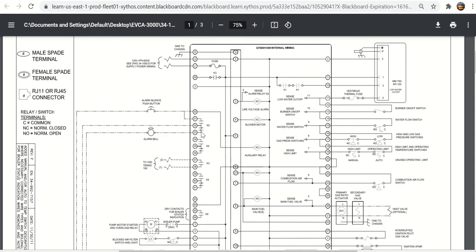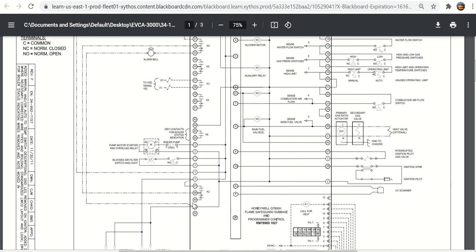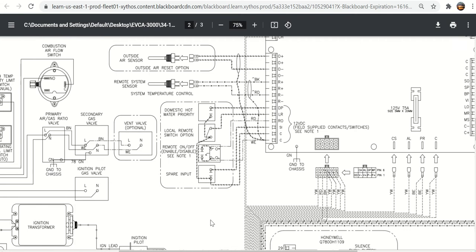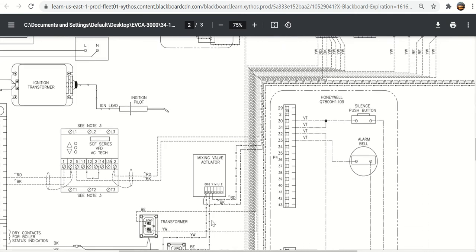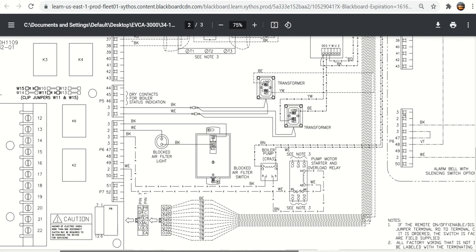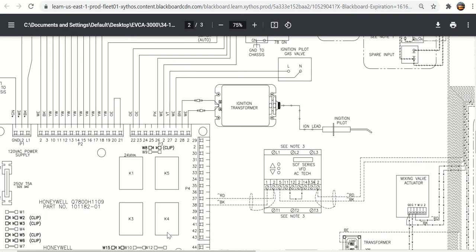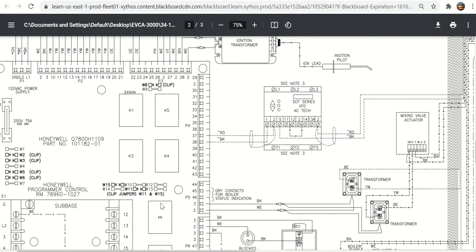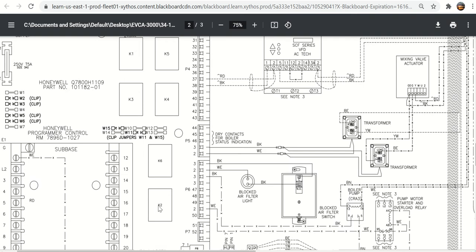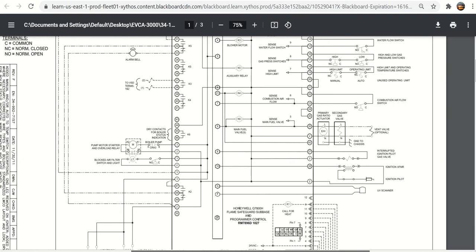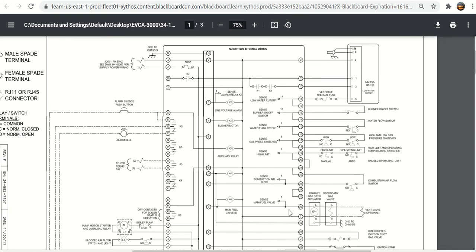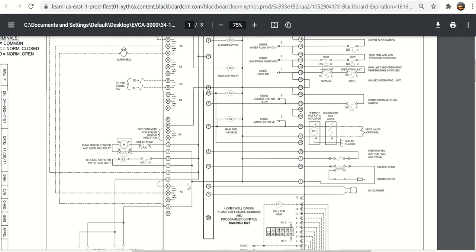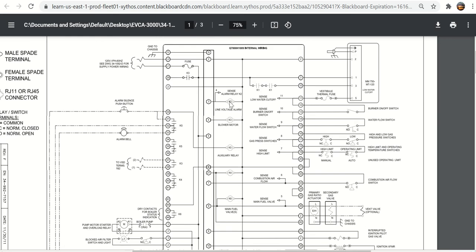I want to go over this alarm silence, alarm bell circuitry here. When you looked at this drawing down here on the circuit board where the 7800 subbase is, you see all of these K1. These are all relays. You saw K2 was the alarm relay, K5 was the blower relay. Here you have K2, which is the alarm relay.